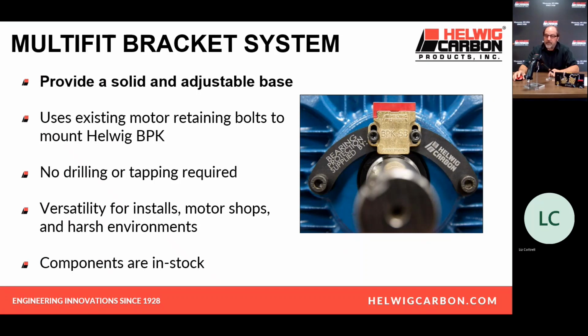Here's another good example of that multi-fit bracket. We have them for a variety of standard kits, and we have more generic versions because there's 1,000 different kinds out there, but we don't make 1,000 brackets. We make brackets that are adjustable this way, and this way. So you can use an existing motor bolt, install, walk away. Very, very quick for motor shops and out in the field, very quick. Never have to pull a motor apart or pull it off of its load and then have to realign, drill, tap, all that stuff. That's all things of the past.